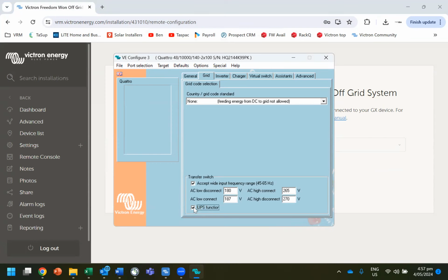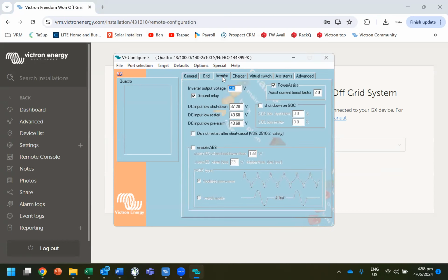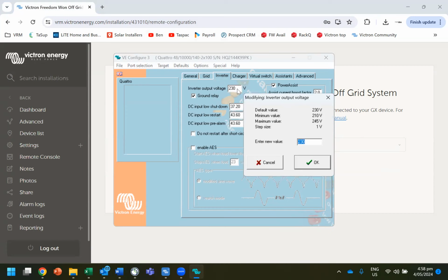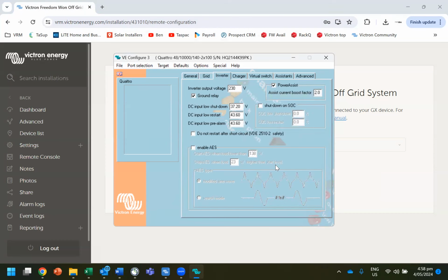So you can tick it or untick it. Generally, I'll untick it, but I'm going to make the assumption that the generator is working okay on this site. But if it's not working okay and it disconnects a lot, or it doesn't even connect, then untick UPS, and that may help it. So on the inverter side of things, we need to say what voltage the system is going to be at. Let's say the system is a long way from the actual load, out in a shed somewhere by a big array, and there's a big sub-main cable going to the load. You may want to push that voltage up maybe by 10%. But in this case, I'll leave it at 230 volts.